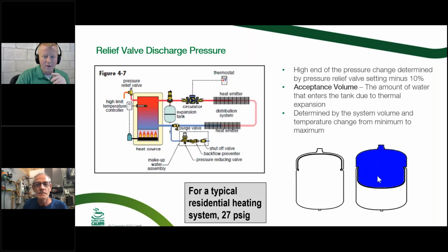We had a good question here about explaining again the minimum and maximum operating pressure in these systems. And we talked about it before. When you're setting your fill pressure in your systems, on hydronic systems especially, you want to make sure you have at least a positive pressure of 5 psi at the top. So that should theoretically be your minimum pressure, to make sure you can at least maintain a 5 psi positive at the top. That makes sure that all of your air vents are going to work properly. The pressure will push the air out of there.